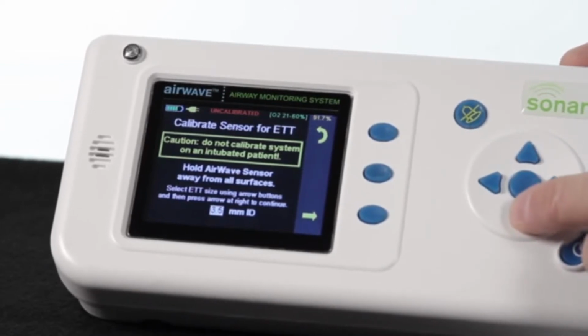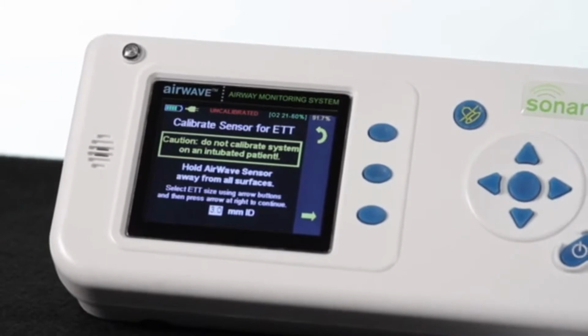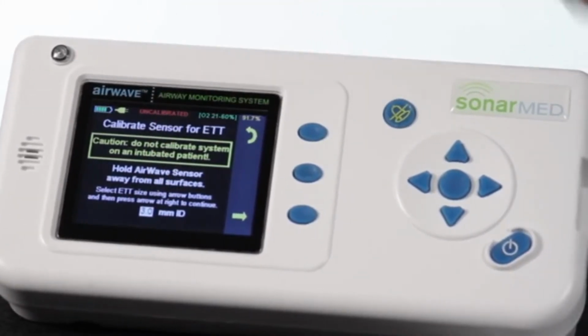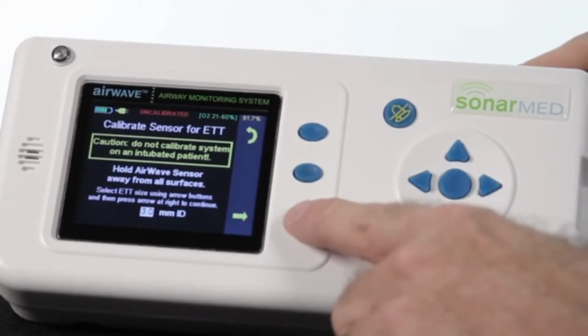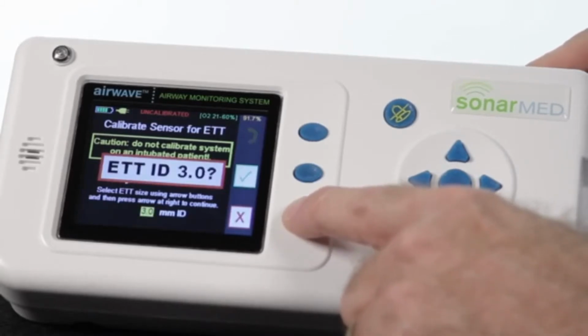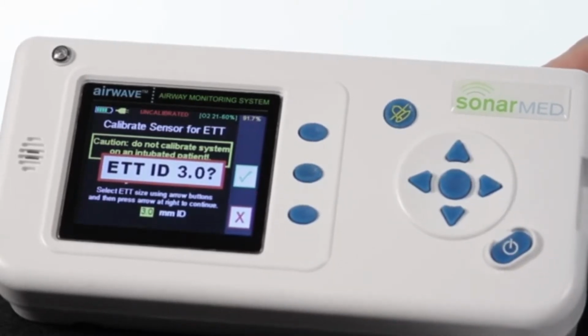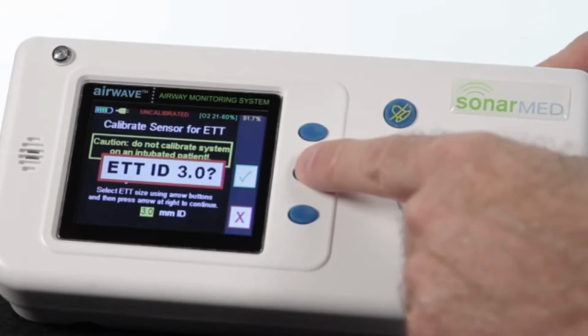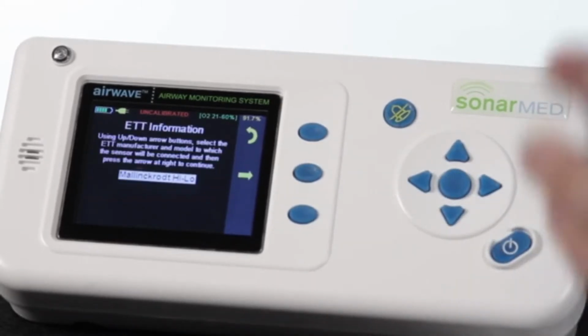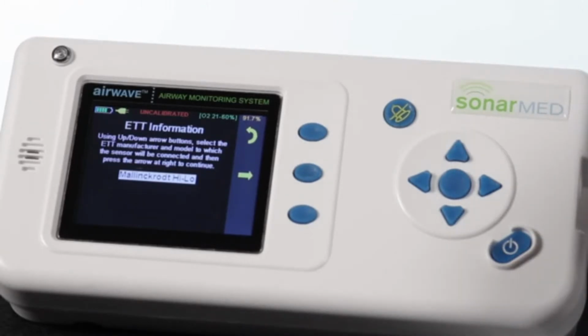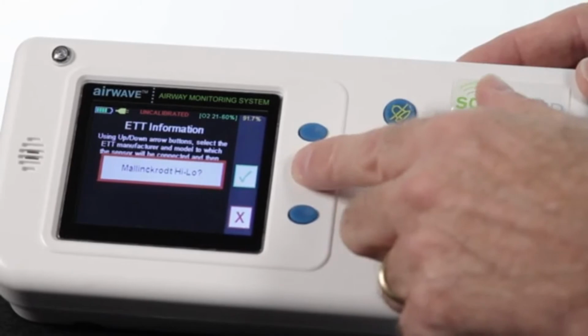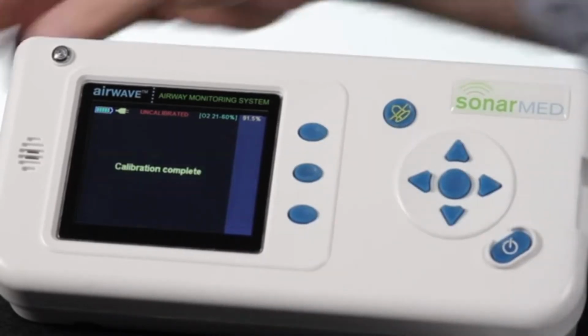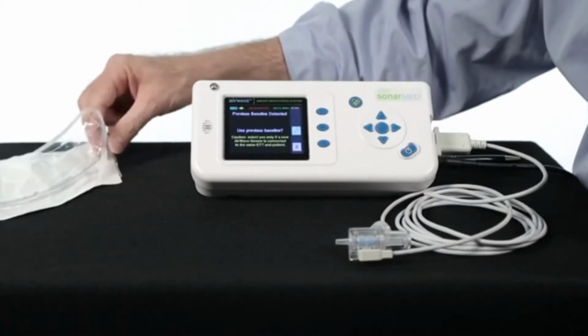So we'll go ahead and take the monitor down so that it reads 3.0, and we confirm that by hitting the button to the right of the arrow. The monitor asks us to reconfirm that we're using a 3.0 tube. We hit the button that corresponds to that, and now we're calibrated. The monitor is asking us the type of tube we're going to be using. It happens to be for this demonstration a Mallinckrodt, so I'll confirm that. And then we'll hook up the endotrach tube.